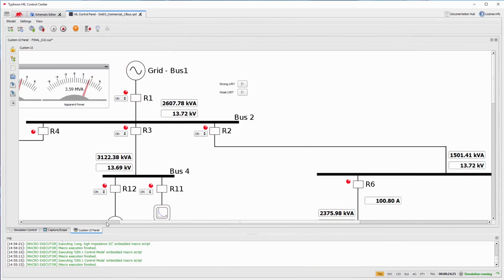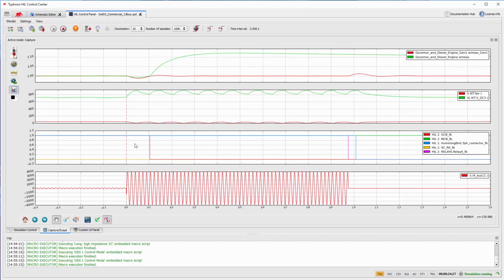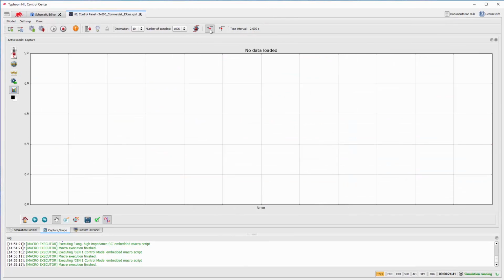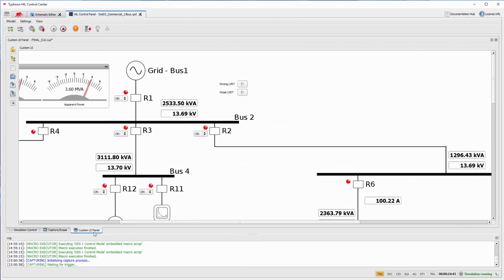To execute the LVRT, we change the amplitude values of the three-phase voltage source that represents the stiff grid according to the profile desired. To help us capture the event in the moment it occurs, we set a variable called LVRT probe right before the fault and use it as a trigger for our capture. So let us enable the trigger and cause the weak LVRT.